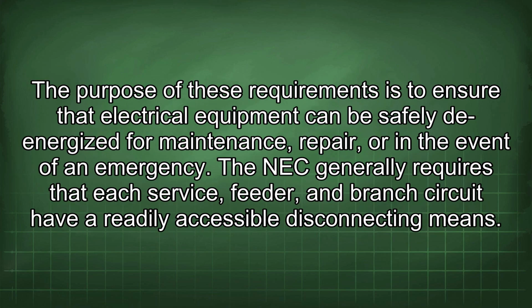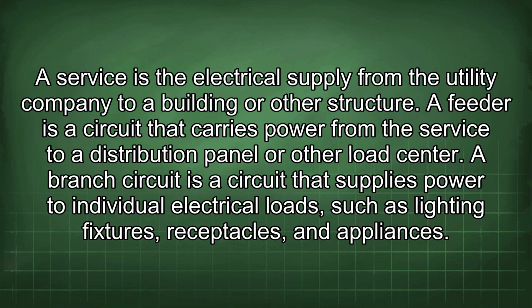The purpose of these requirements is to ensure that electrical equipment can be safely de-energized for maintenance, repair, or in the event of an emergency. The NEC generally requires that each service, feeder, and branch circuit have a readily accessible disconnecting means. A service is the electrical supply from the utility company to a building or other structure. A feeder is a circuit that carries power from the service to a distribution panel or other load center. A branch circuit is a circuit that supplies power to individual electrical loads, such as lighting fixtures, receptacles, and appliances.